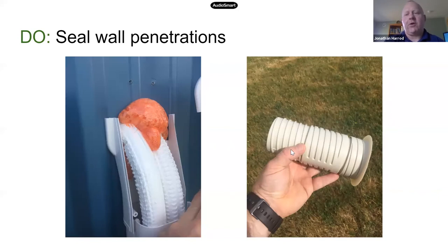On the right, we have a device called a wall sleeve, and we strongly recommend that these be installed every time we're running piping through a wood frame wall that's full of something like fiberglass or cellulose, because you can't really get a good seal spraying the spray foam into those soft and fibrous materials. And so we insert this little telescoping sleeve. It forms a nice tight seal and holds the spray foam in and gives you a much better seal overall. And they cost about $10 a piece, but they are, you know, a really good thing to add to your work scope.